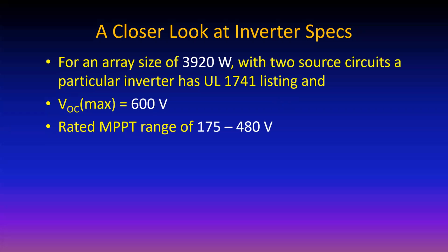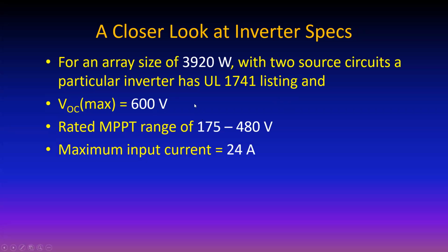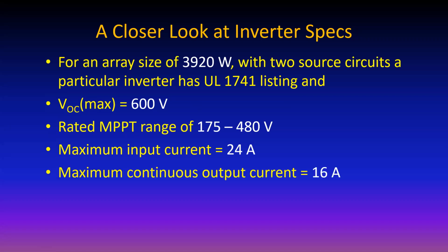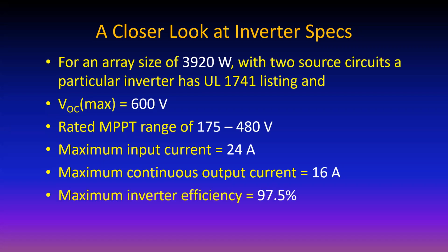So here's an inverter. What else are we doing? Its maximum input current is 24 amps. Well, we're good because the modules themselves, the current is somewhere in the neighborhood of 9 amps. So the 2 strings in parallel is around 18, so we're good on that. Maximum continuous output current of this inverter is 16 amps. And that's an interesting number because 125% of that is exactly 20, which means you can have a 20 amp circuit breaker. And the maximum efficiency of this inverter is 97.5%.